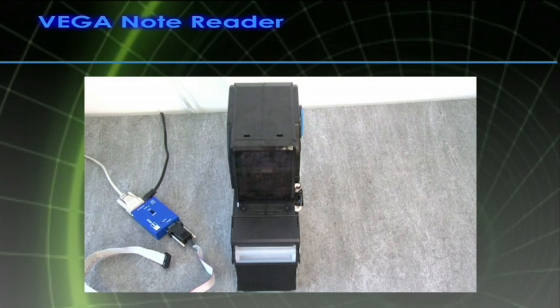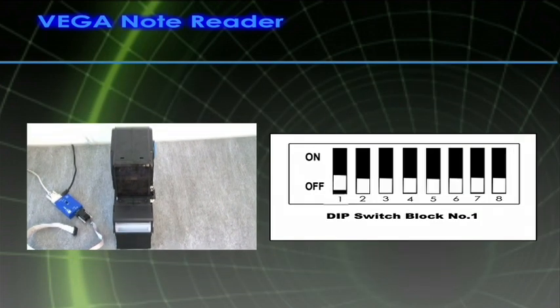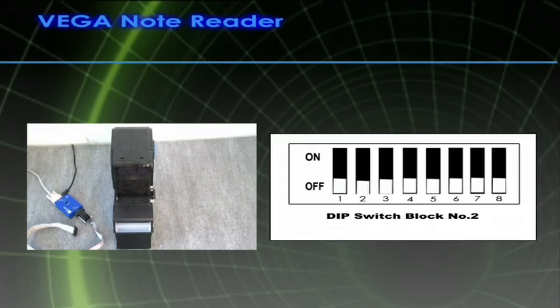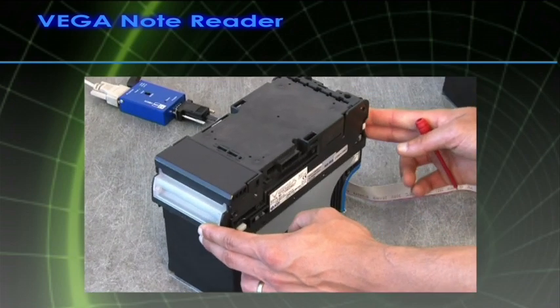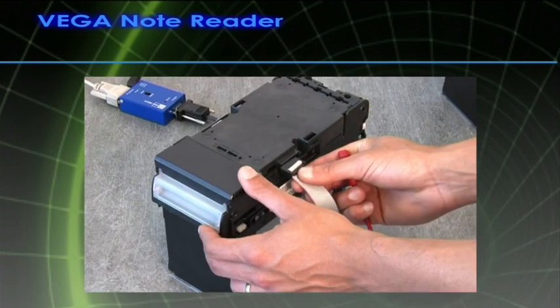In order to verify if the 8 sensors within the Vega unit are fully functional, perform the following procedure. Please ensure that the Vega unit is powered off. Set dip switch block number 1, switch number 1, number 2, number 3, number 4 and number 5 to on. And dip switch block number 2 switches are all off. Turn the Vega unit power on.